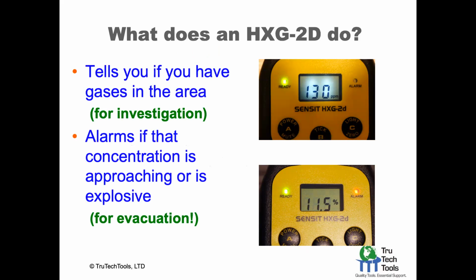So you can see the upper screen display, it's got 130 ppm gas. We talked about how it switches over between reading ppm up to 990, and then when you get higher concentrations, it'll move to percent gas. So this is percent gas, 11.5% gas, which is well above for methane, the 5% level, and well above for propane, the 2.15% level. And you can see, maybe you can see, but the alarm will be going off and you'd hear an audible alarm.